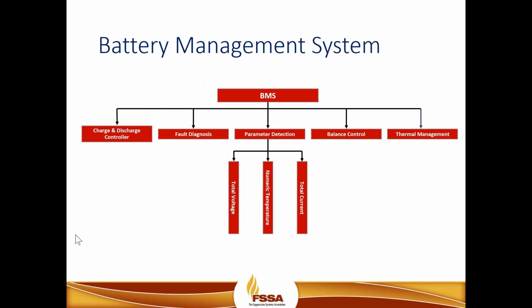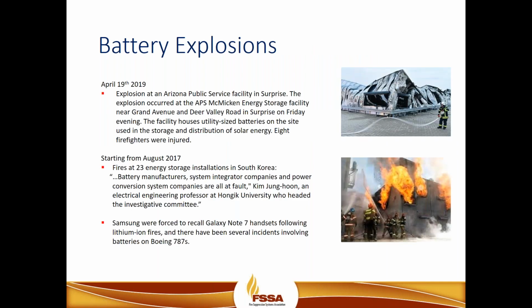identify are the charging and discharging and the controllers, maybe faulty diagnosis of the battery management system, maybe looking at the parameters of detection. So maybe the battery management system has to review the total voltage, numeric temperature, and current, total current all at the same time. So if maybe there's a malfunction in the battery or the battery management system and it's not able to identify this through balance control and thermal management, it needs additional support mechanisms in place to act as not just a redundancy factor, but also to assist in identifying possible thermal runaway events.